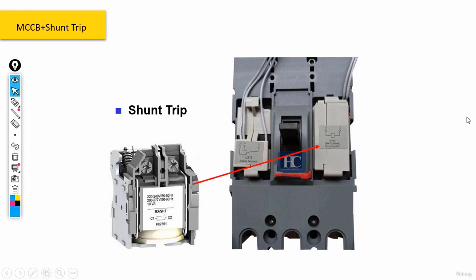Guys, if you remember, when we were discussing MCCB breakers, we said that inside these breakers, an equipment called Shunt Trip would be set. Now, if we connect a signal to both sides of this relay here, let me point them out, talking about these two, okay? This could cause the MCCB breaker to be set on the trip mode. I write it down. Now, guys, the thing is, we can use all of these mentioned equipments: CBCT transformer, Shunt Trip, and also MCCB breaker for further protection regarding our motor. How? Let's see. Let me move to the next slide.